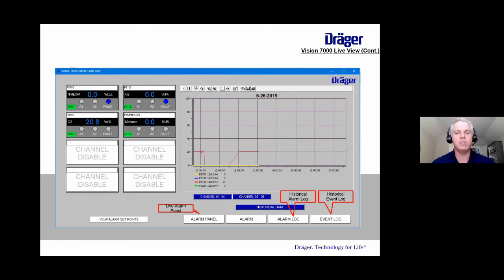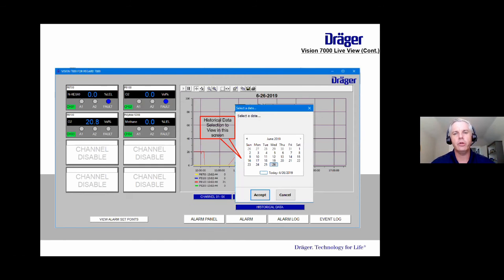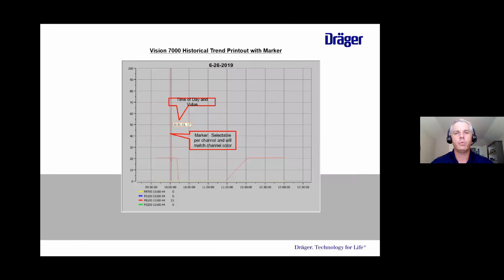So you have event logs, a live alarm panel. You can actually select a date to go back in time to look and see what's happening on that particular day. You can do all that through the Vision 7000. That's reading real-time information from the ReGuard 7000 system. Like I mentioned, you can see the time of day, and if you move that bar around, you can actually change the times versus potentially change the values that you're seeing.